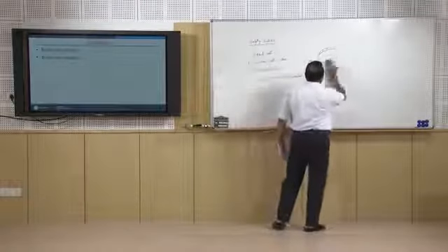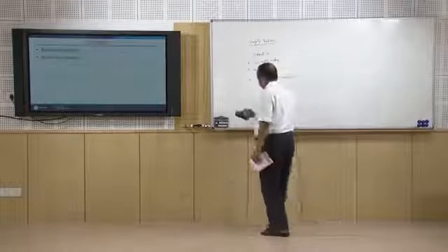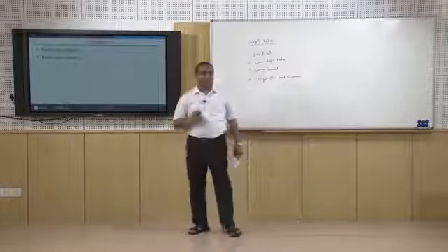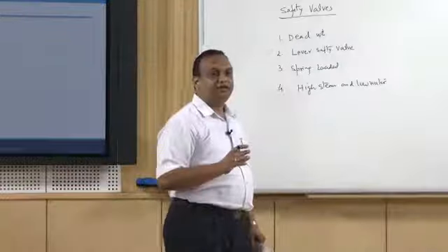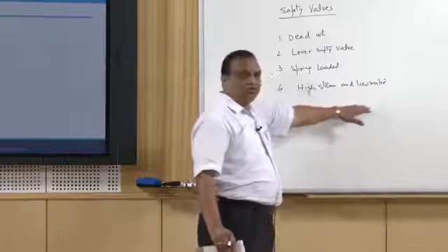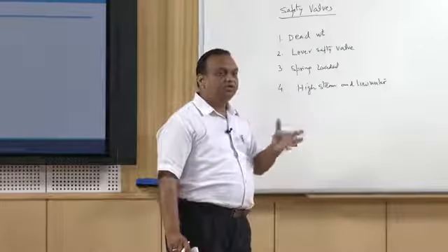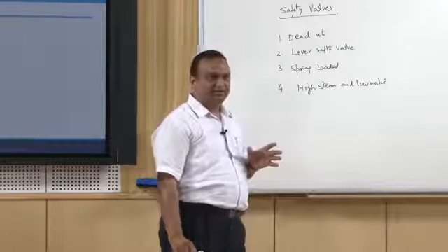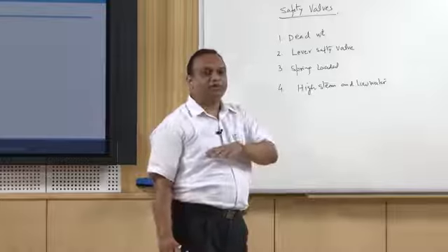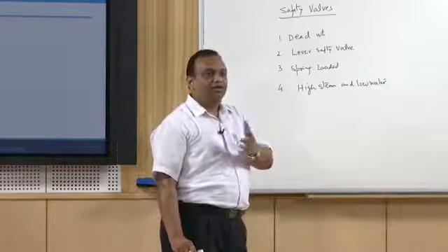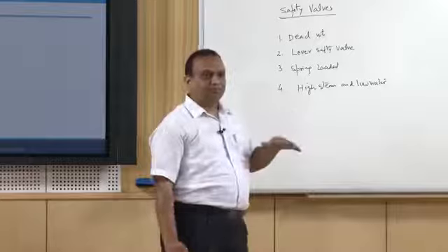Now, the fourth one is high steam and low water valve. It serves two purposes. First, when the pressure of steam is high, steam will be vented off. When the water level is low, in that case also some indicator has to be there, so that the operator who is sitting in the operation room may know that there is a low level of water, right.